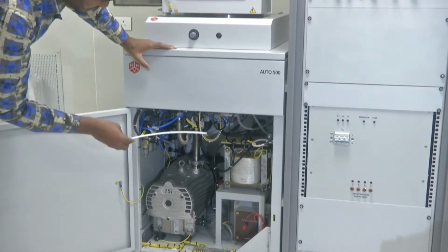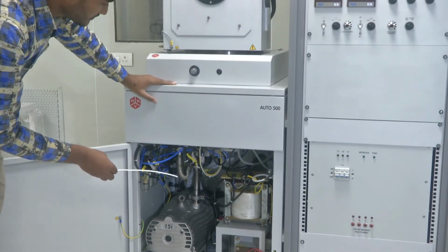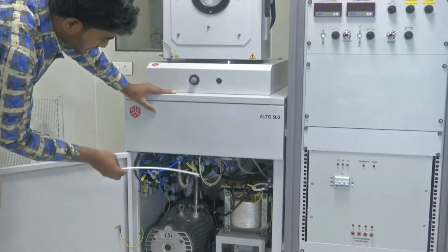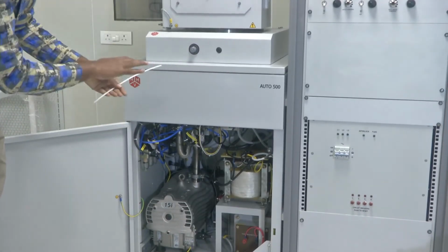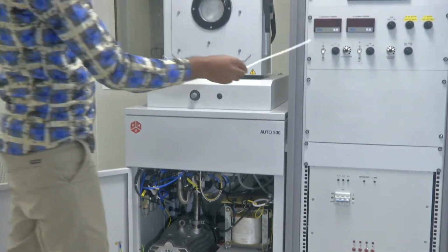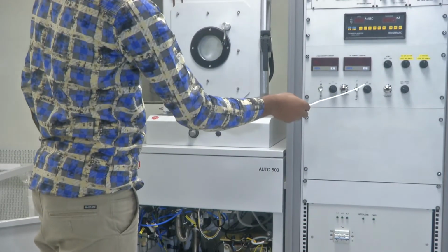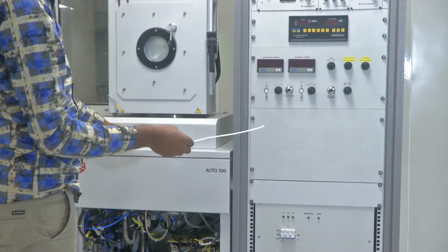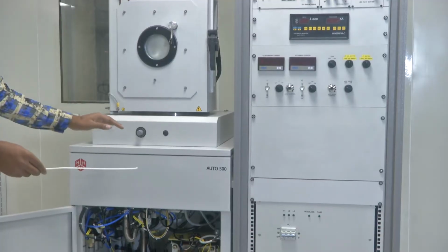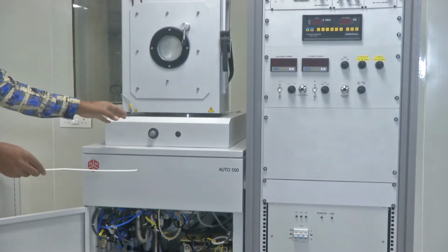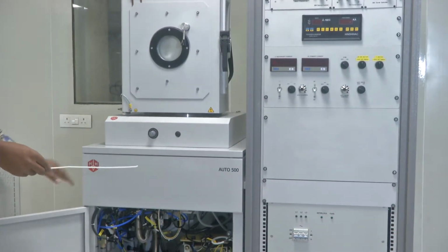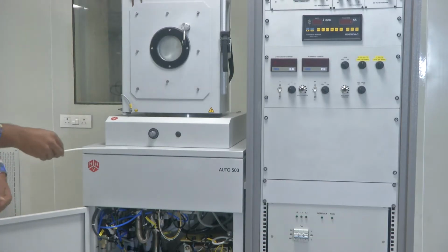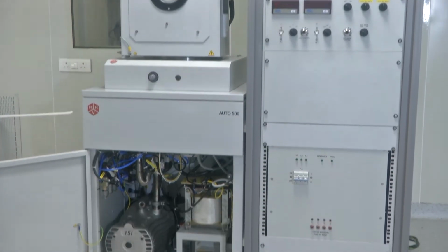This is the chamber, an Edwards make, imported. In between the chamber and the turbo pump, one valve is there. That is called the high vacuum valve. After achieving a certain vacuum level, we will go for that high vacuum valve. So manually we have to open the valve.